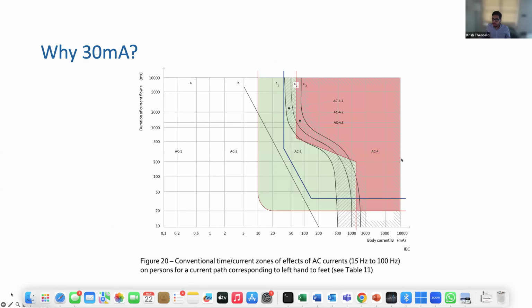It's an excellent question. So I'll refer you to the standard IEC 60479 part 1. Now, you're right, these currents are dangerous, but the effect of the current depends on the time you are exposed to it. The standard has a current-time graph. On the x-axis is current, y-axis is time. Currents and time exposure are divided into 4 zones: AC1, AC2, AC3, and AC4.